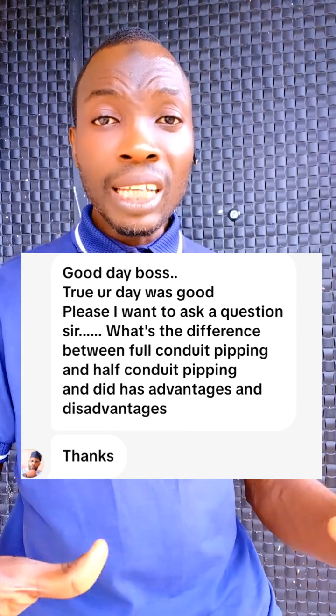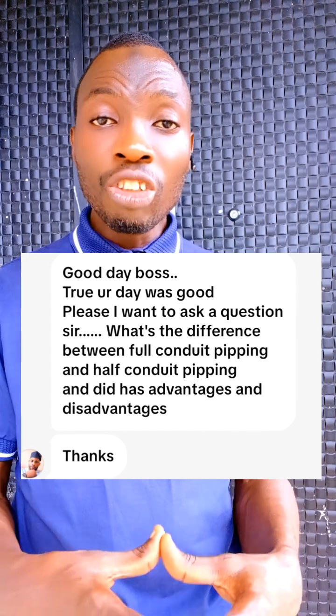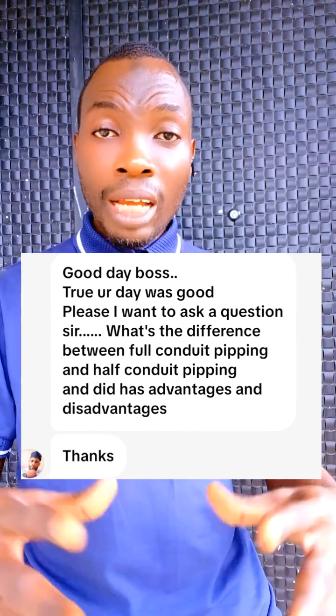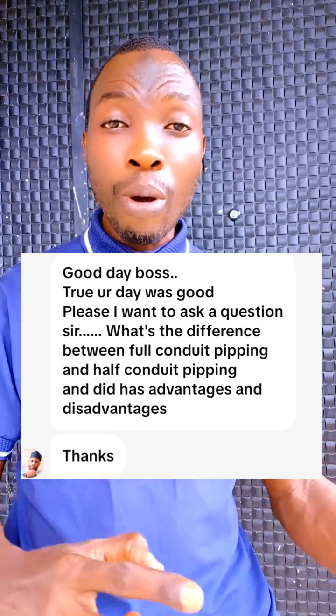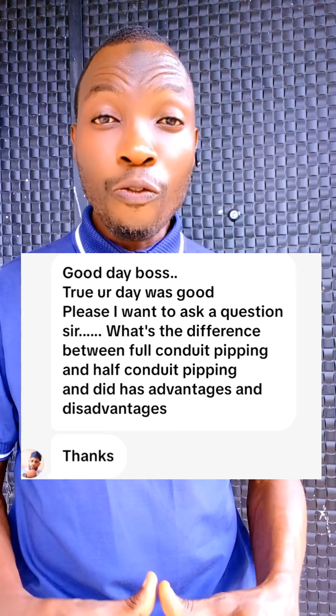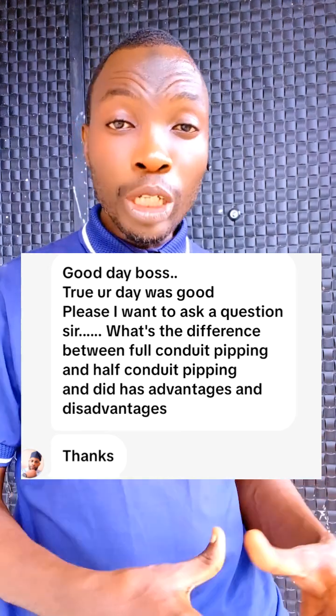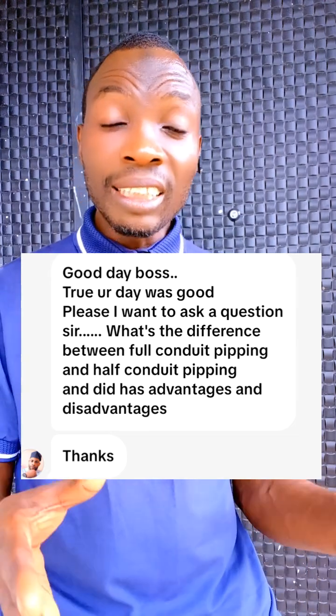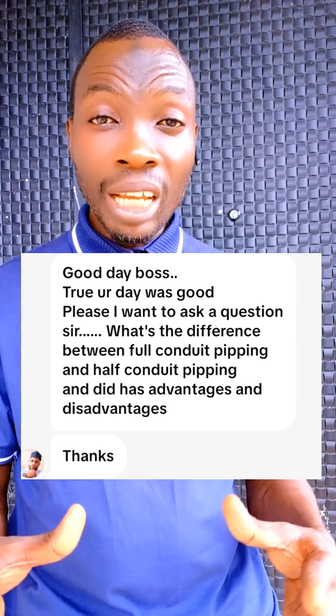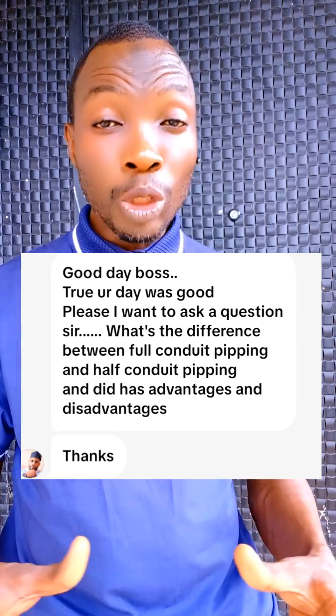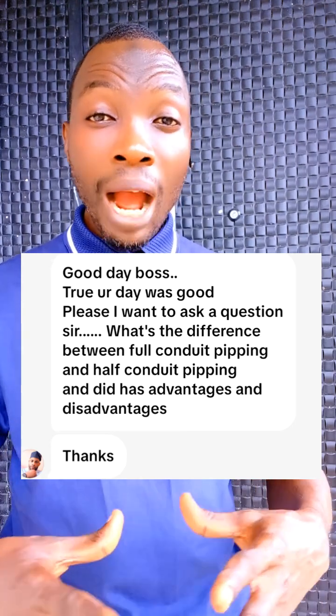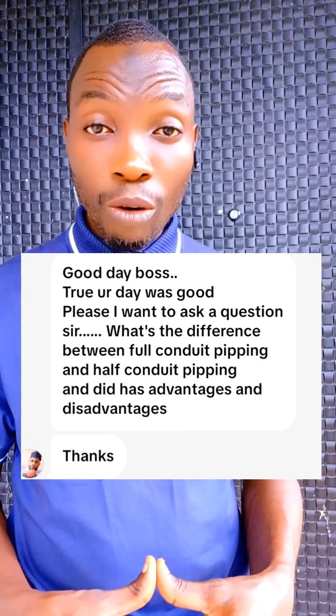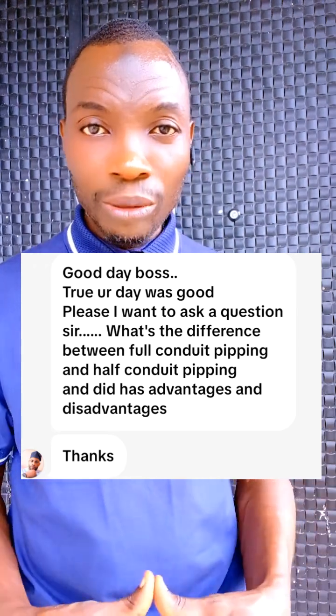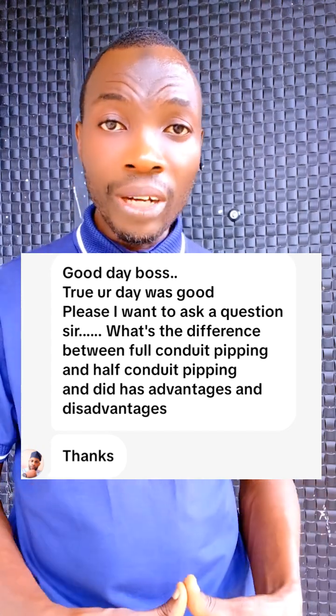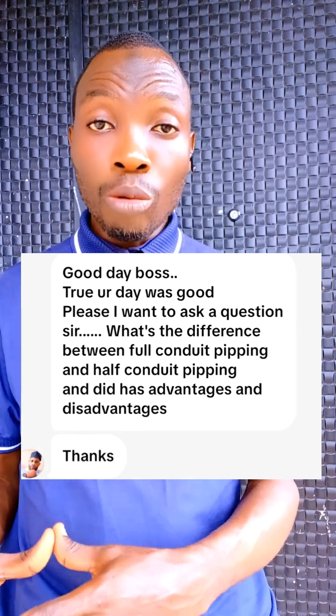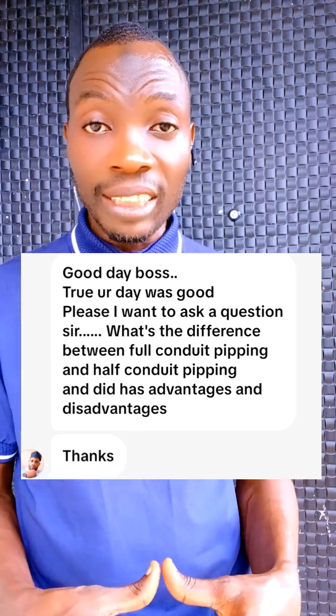A full conduit is a type of conduit system in which cables are concealed in the pipe and routed from one point to another within the installation fully, whereas a half conduit installation system is a system whereby cables are only concealed in the pipe in order to route them through the walls, but in the roof, cables are left dangling, laying on the roof, unprotected, unconcealed. Both methods are common in electrical installation. Each of the two has advantages and disadvantages.